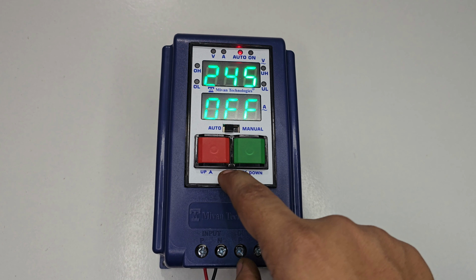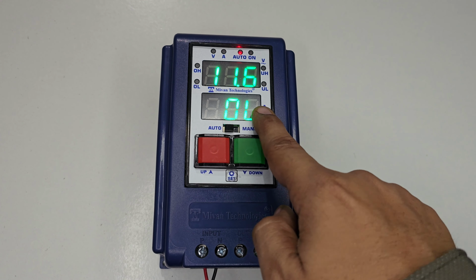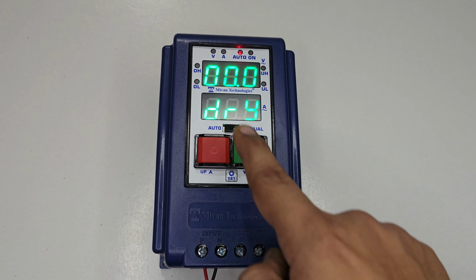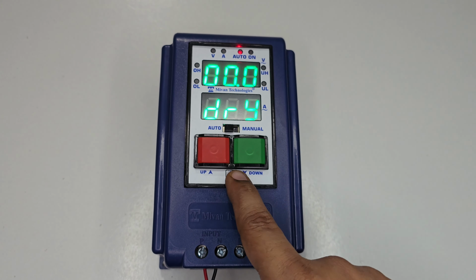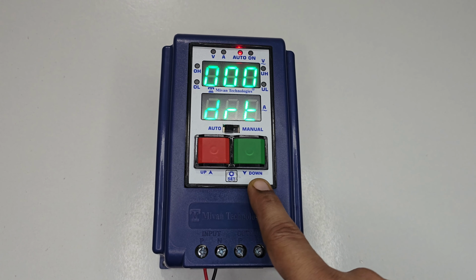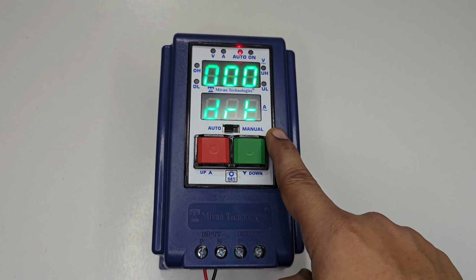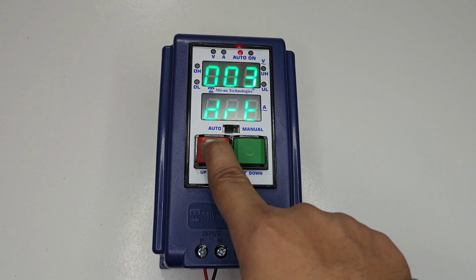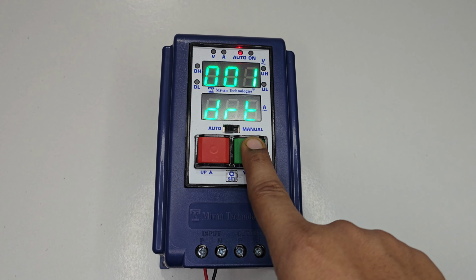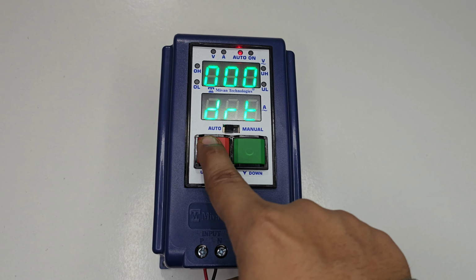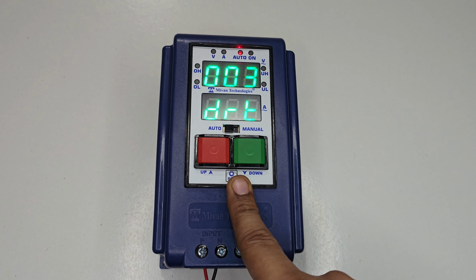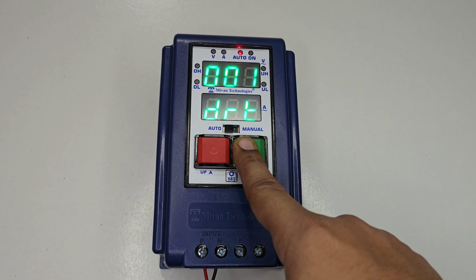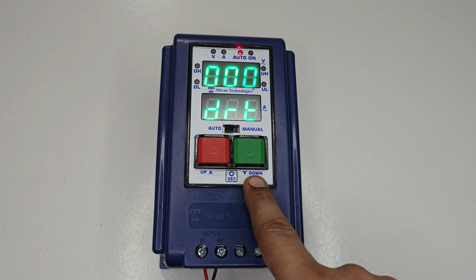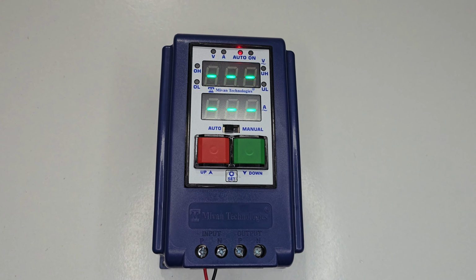Now in the main menu, press the set button, you can see the overload current. Press the set button, you can see a dry current option. Press the set button. Here you can see a dry run reset timer option. You can adjust the dry run reset time by pressing the up and down key. This dry run reset time is in minutes. You can adjust it to whatever time you want and press the set button to store the value.